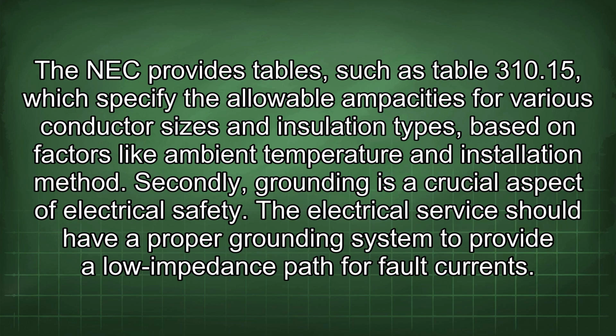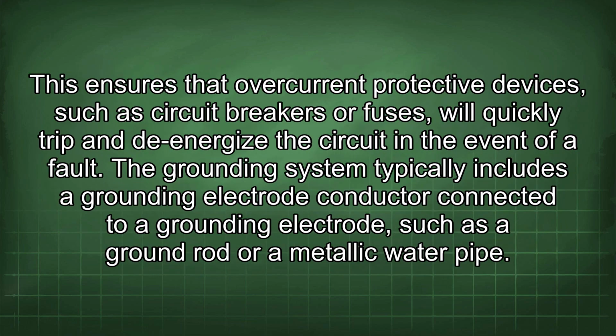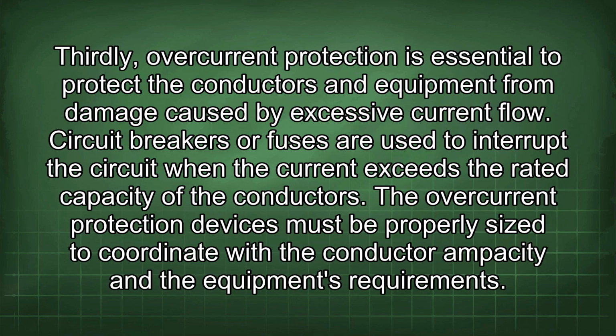Secondly, grounding is a crucial aspect of electrical safety. The electrical service should have a proper grounding system to provide a low impedance path for fault currents. This ensures that overcurrent protective devices, such as circuit breakers or fuses, will quickly trip and de-energize the circuit in the event of a fault. The grounding system typically includes a grounding electrode conductor connected to a grounding electrode, such as a ground rod or a metallic water pipe.